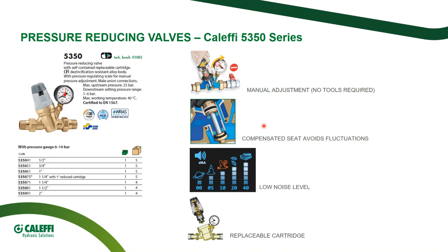What else? They have to be user-friendly. So the setting of the valve has to be very, very easily reached. This is why this family of pressure reducing valves can be calibrated without the aid of any tool. It is enough to rotate the upper part of the handle, and there is a special dial to see the presetting. Pressure reducing valves have to be silent, so they have to grant comfort to the user. If we imagine a hotel and every single washroom is equipped with a pressure reducing device, they don't have to generate vibration or noise. This is very important.